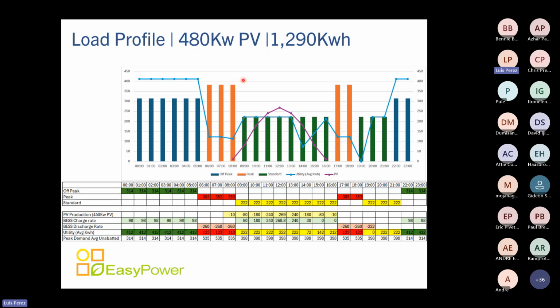You have your typical peaks, right? People come in the mornings and they cook and shower and go to work, and then you have another peak in the evening as people come back from their offices. We have superimposed on that a curve with the PV production on a low angle array on carports and how it looks against the standard time demand. The blue line is essentially what the utility sees after all of this is done. What you can see here is that the utility sees a slightly higher demand in off-peak time, because physically we are charging the battery during this whole period from 22 hours to 5 in the morning.